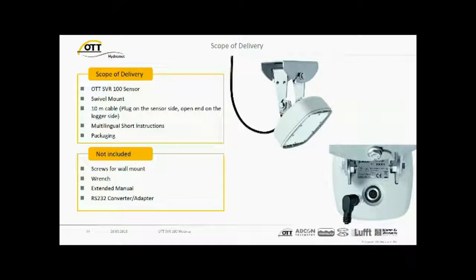to communicate with the sensor via the OTT SVR 100 user software, and if you want, for example, to upgrade the instrument with a new firmware. It's not our target to have a new firmware for you every month. No, don't fear this. But if it is required at some time and you want to communicate and upgrade by yourself, you will need this converter. We have this in the price list, so no problem.